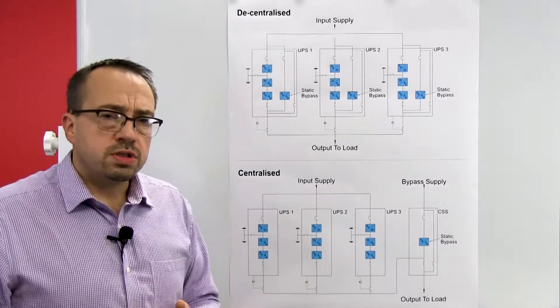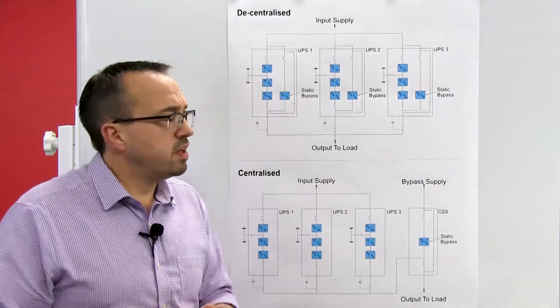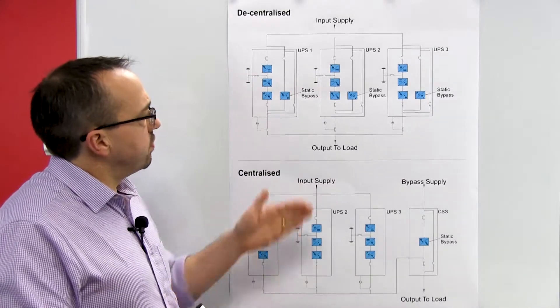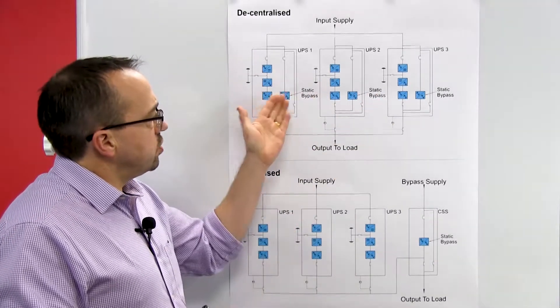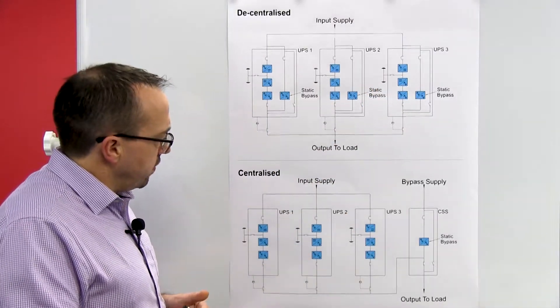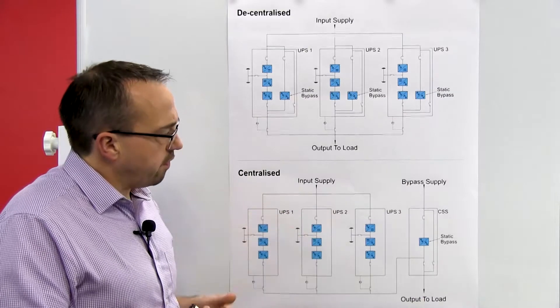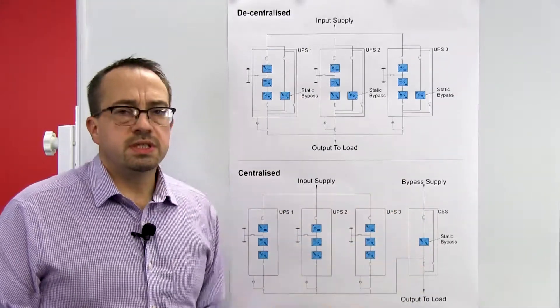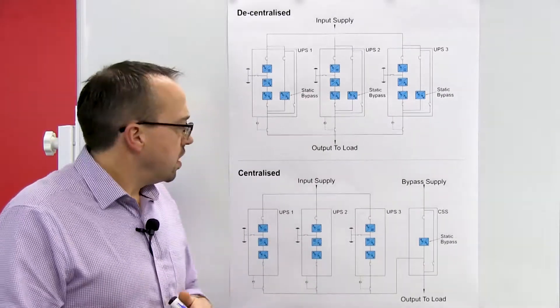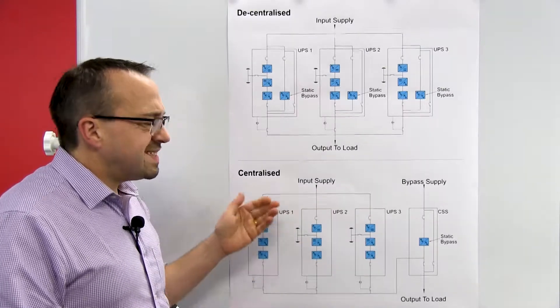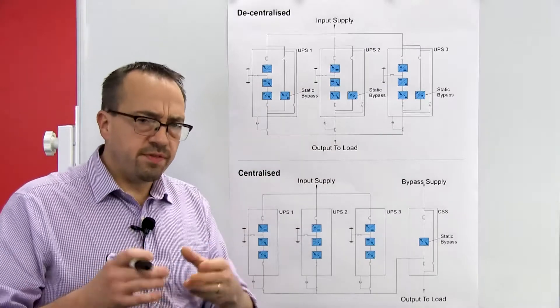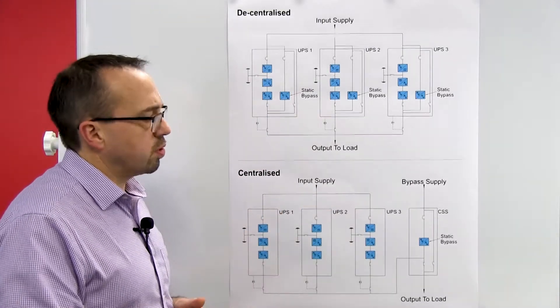Firstly, let's look at costs. In terms of costs we can look firstly at the actual UPS units themselves. In the decentralized system you have three UPS systems each with their own static bypasses. In the centralized system you again have three UPS modules, however there is an additional fourth cabinet containing the static bypass and all of the controlling architecture. The centralized bypass solution is typically slightly more expensive than the decentralized approach.